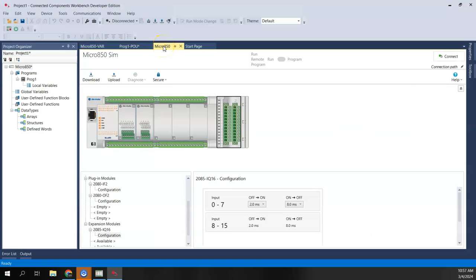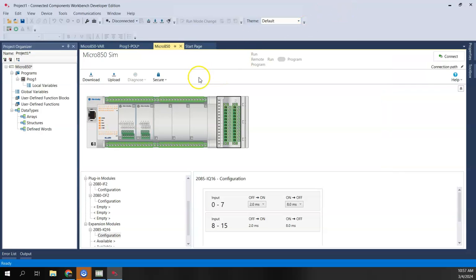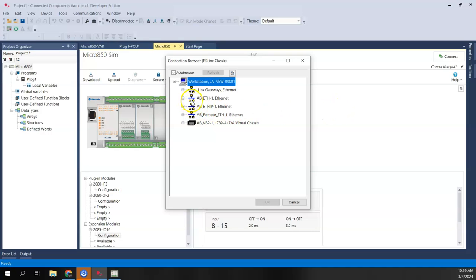Now we're ready to connect. The virtual simulator is up and running — very important that it's running and has an IP address set. Back in CCW, I don't have a connection path defined yet, so I'll click Connect. In the connection browser, I go to ETH-1 (Ethernet) and I can see the 127.0.0.1 Micro 850 controller. I'll highlight that and click OK.